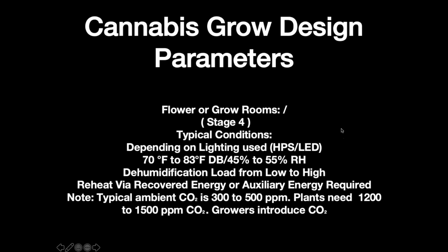One of the things that they do in the grow rooms is they introduce CO2. Your normal ambient CO2 in the atmosphere is 300 to 500 parts per million. The plants need 1,200 to 1,500 parts per million, so the growers are introducing CO2 to the space. In some cases, they'll do this by actually open flame in the space. Most of them, though, are actually going to stored canisters outside. You'll see a tall CO2 bottle on the outside, and then the CO2 is injected into the building. We can actually inject that CO2 through our air handlers, but in most cases, the CO2 people are introducing that through their own system.